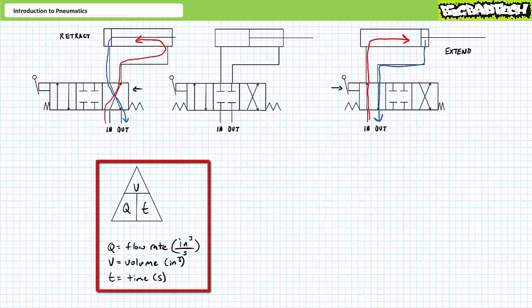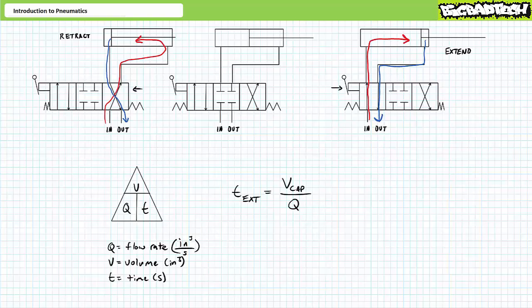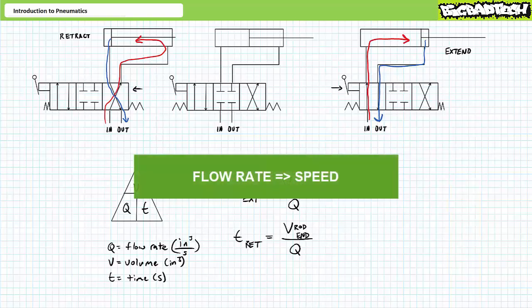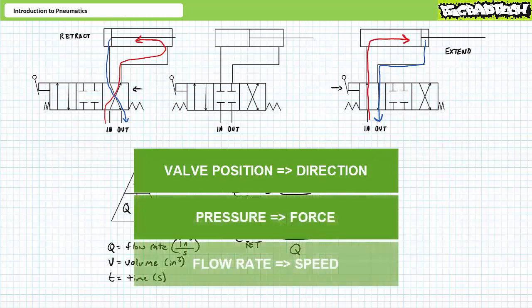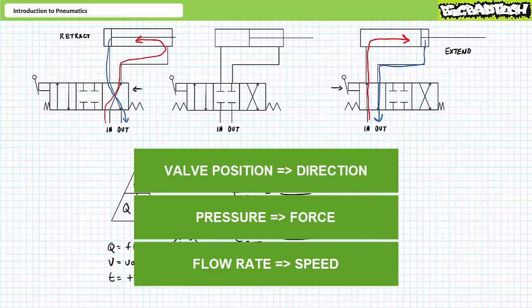Lastly, actuator speed is dependent upon flow rate. Flow rate Q is a measure of volume per unit time. To calculate extension time, one would divide the full cylindrical volume of the cap end by the incoming flow rate. Similarly, to calculate retraction time, one would divide the smaller tubular volume of the rod end by the incoming flow rate. Any increase in flow rate or decrease in volume results in shorter extension and retraction times. Conversely, any decrease in flow rate or increase in volume results in longer extension or retraction times. In summary, flow rate determines the speed of fluid power. This is true for both hydraulic and pneumatic systems.